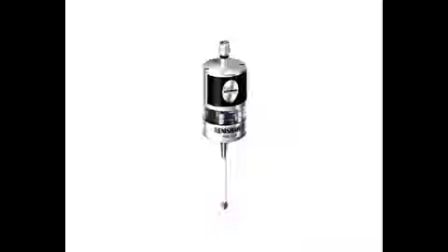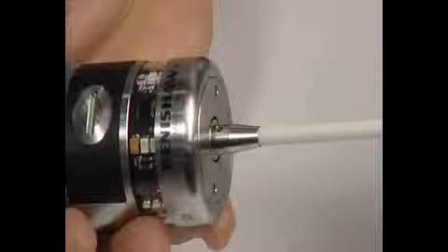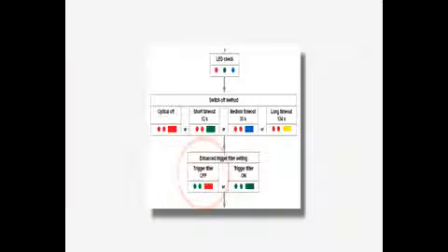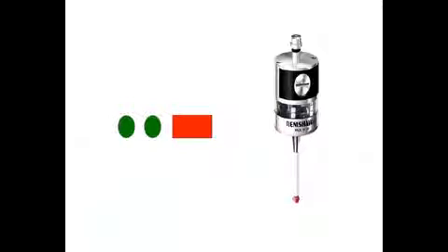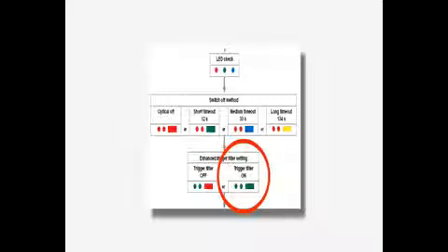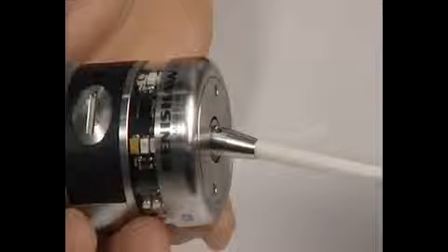Probes subjected to high levels of vibration or shock loads may output signals without having contacted any surface. The enhanced trigger filter improves the probe's resistance to these effects by adding a trigger output delay to the trigger signal. To change the trigger filter, deflect the stylus for 1 second. Green, green, red. Trigger filter off. No trigger filter is used. And green, green, green. Trigger filter on. A 10 millisecond delay is added to the output signal. To move to the next option, the stylus should be deflected for at least 4 seconds.